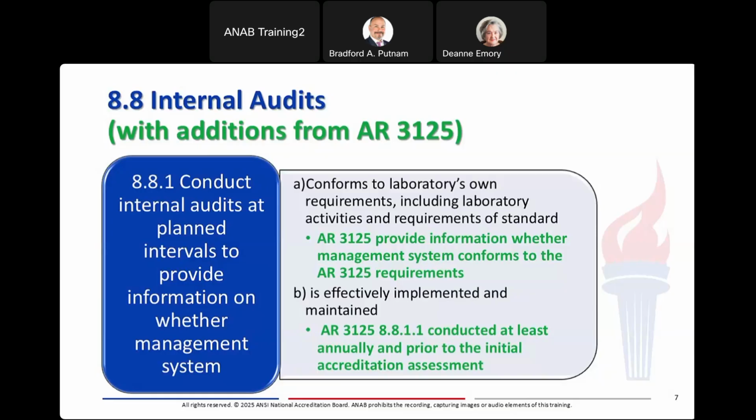So ISO 17025 states that internal audits need to be conducted over planned intervals. However, ANAB AR 3125 states in clause 8.8.1.1 that internal audits shall be conducted at least annually and shall also be done prior to your first assessment.